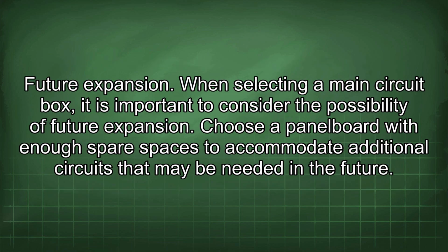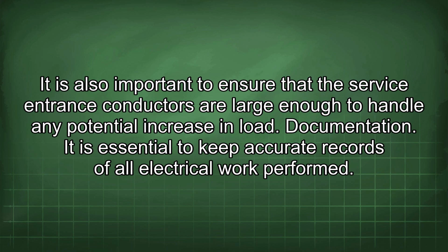Future expansion. When selecting a main circuit box, it is important to consider the possibility of future expansion. Choose a panel board with enough spare spaces to accommodate additional circuits that may be needed in the future. It is also important to ensure that the service entrance conductors are large enough to handle any potential increase in load.